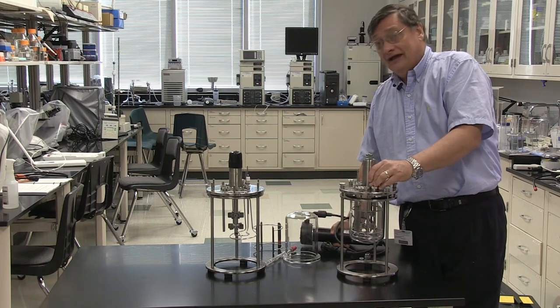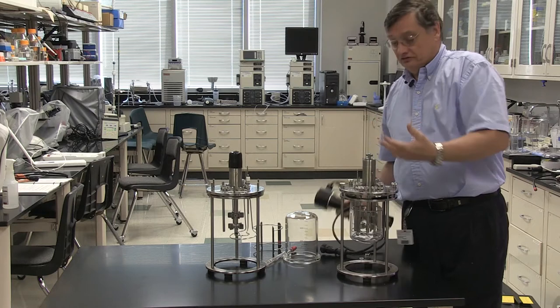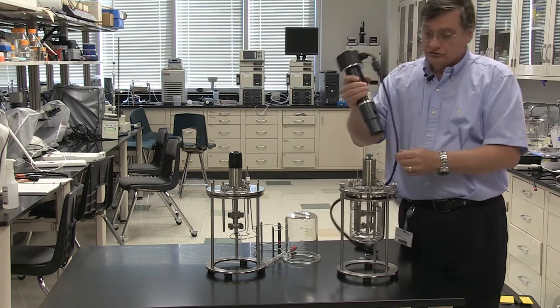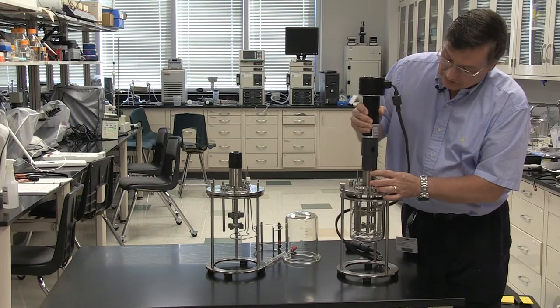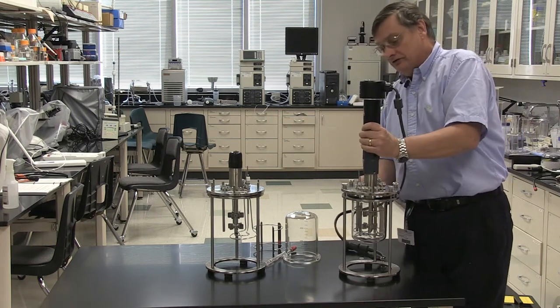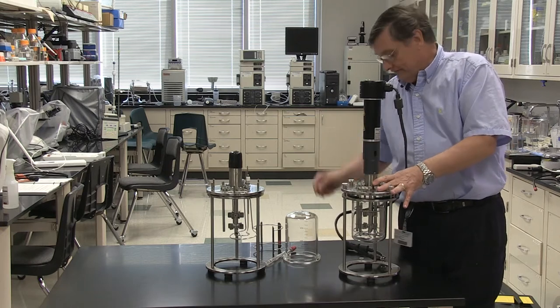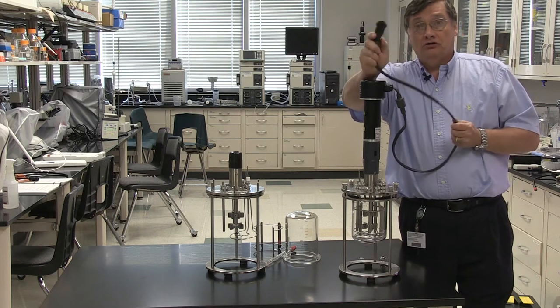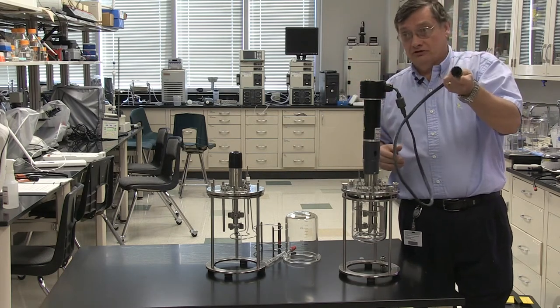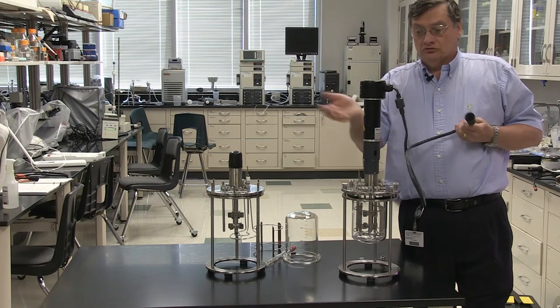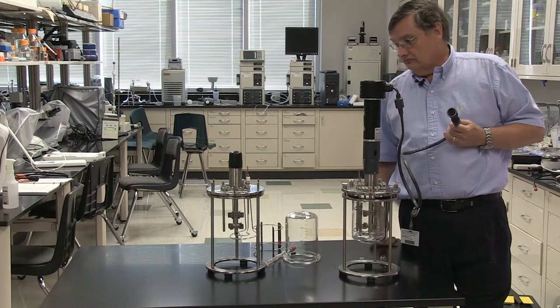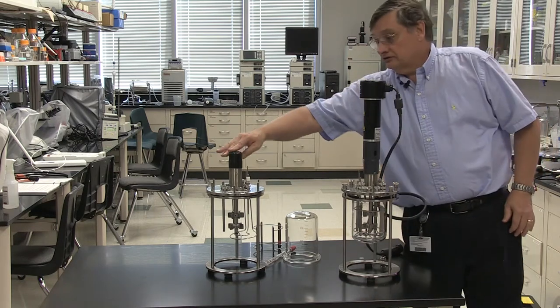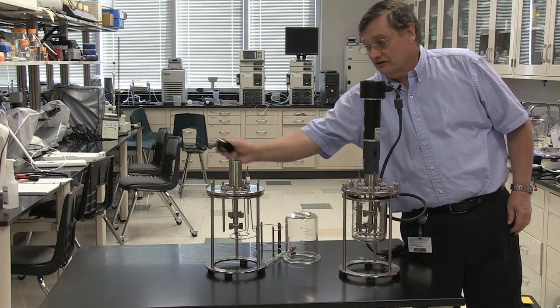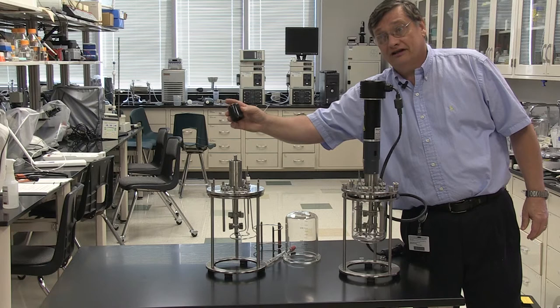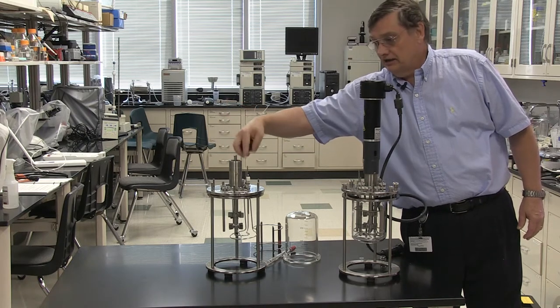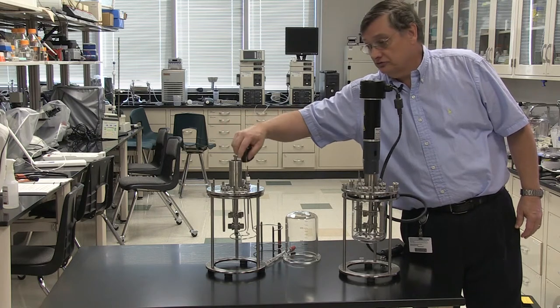It's also referred to as the drive unit because it's part of the drive assembly, and this is the motor that aligns with these pins on the side of the drive unit, and so it'll actually drive the impeller. This unit will then plug in, this cable will plug into the control unit, which will control the RPMs of the motor. This one over here, you can see, has this black piece of rubber over here. That's actually used in place when you're autoclaving the unit to keep moisture from getting into the bearings.